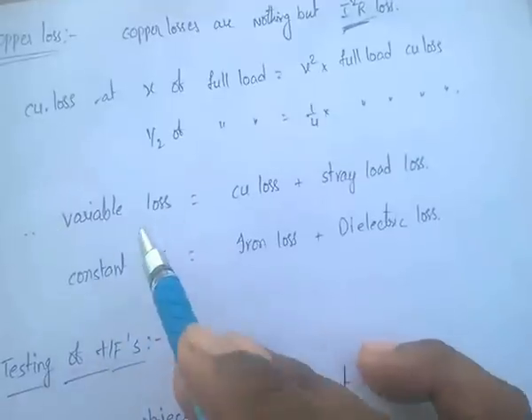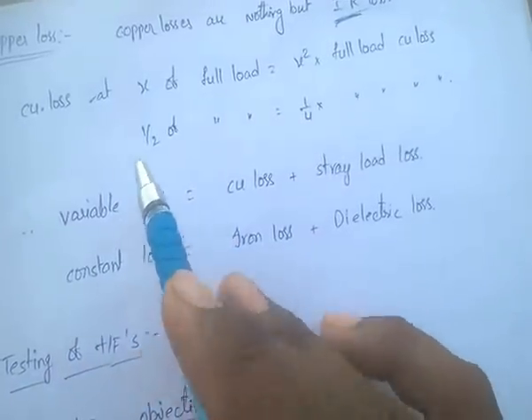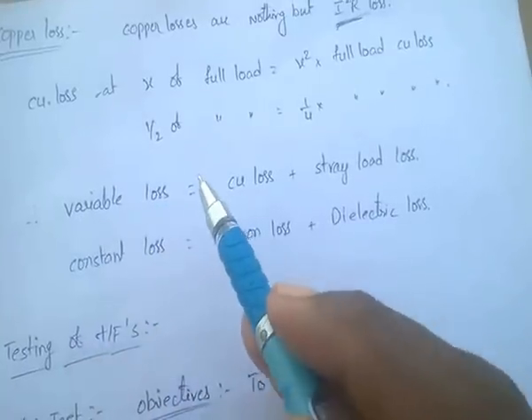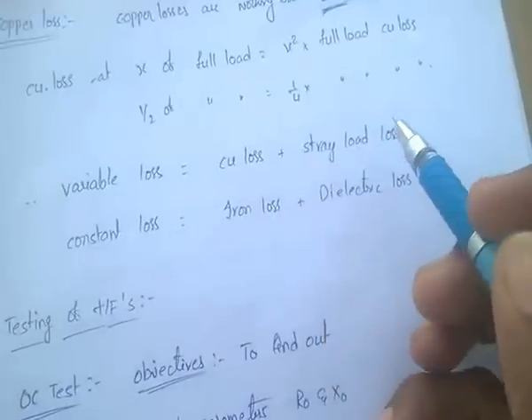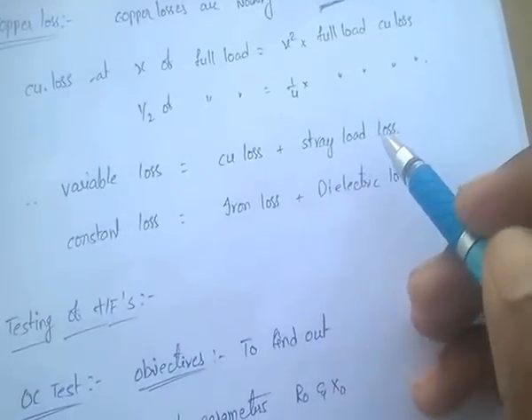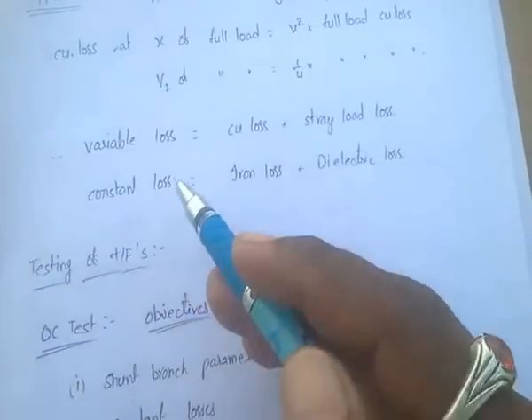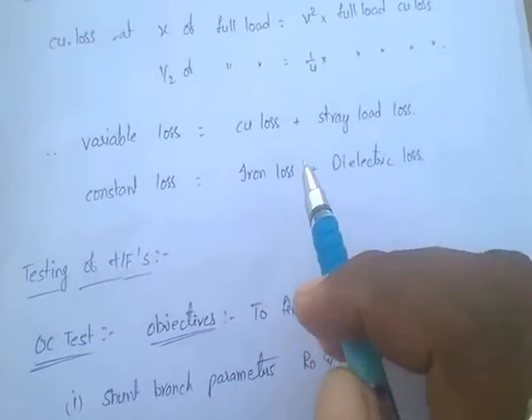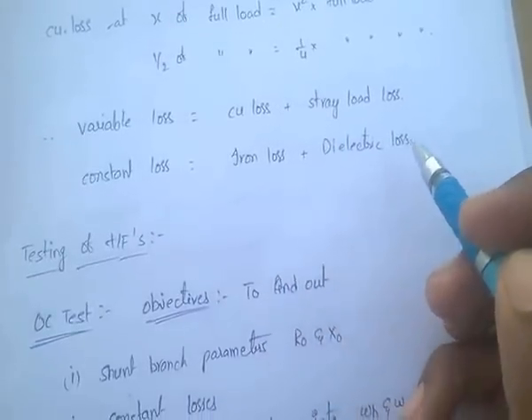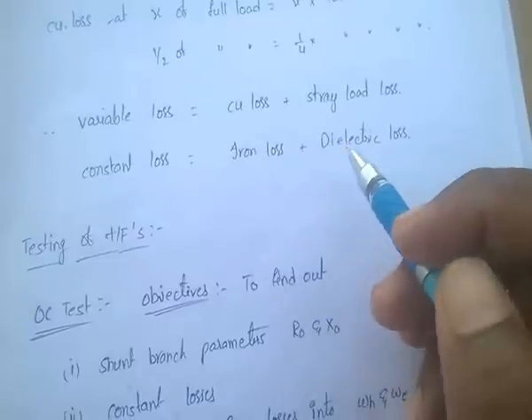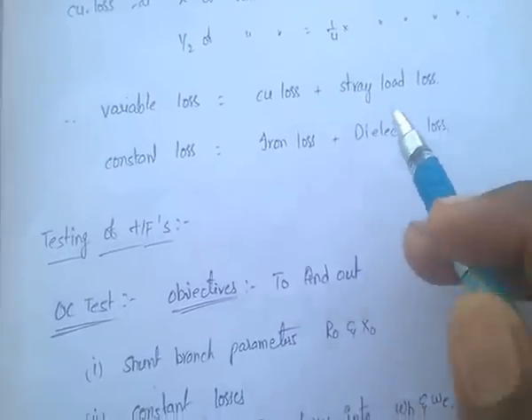Variable losses vary whenever the load varies. Variable loss equals copper loss plus stray load losses, where stray load losses are losses due to other parts of the transformer. Constant losses are iron losses plus dielectric losses. Dielectric losses occur in the dielectric parts of the transformer.